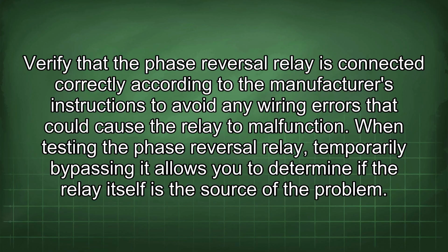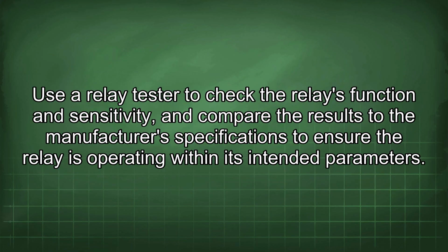When testing the phase reversal relay, temporarily bypassing it allows you to determine if the relay itself is the source of the problem. Use a relay tester to check the relay's function and sensitivity, and compare the results to the manufacturer's specifications to ensure the relay is operating within its intended parameters.